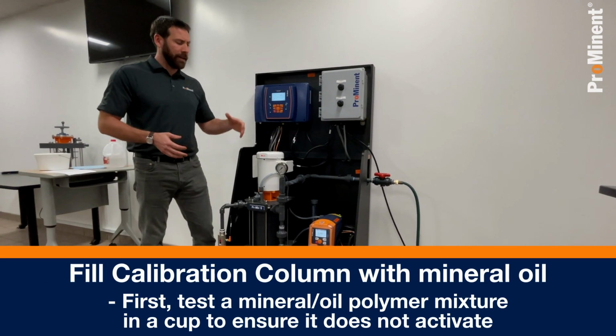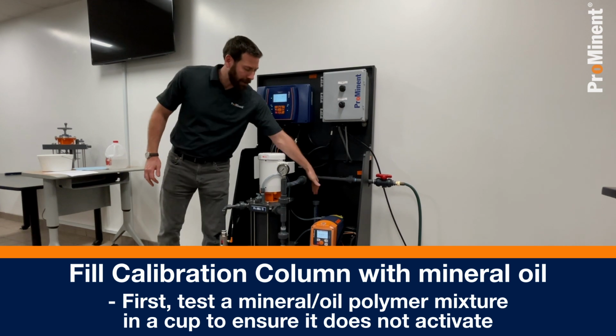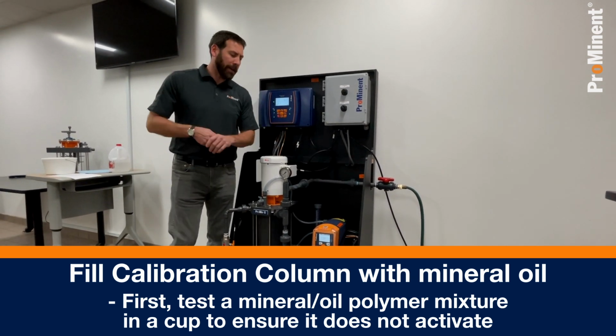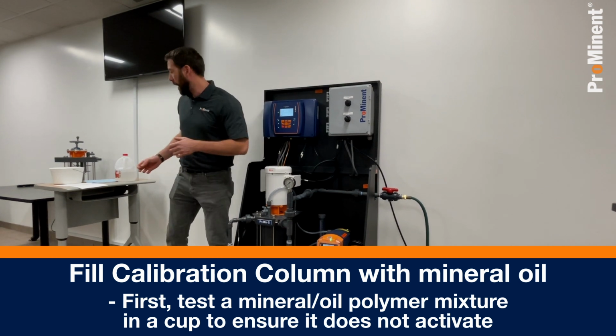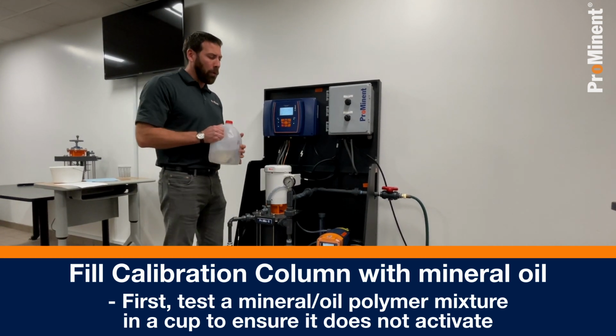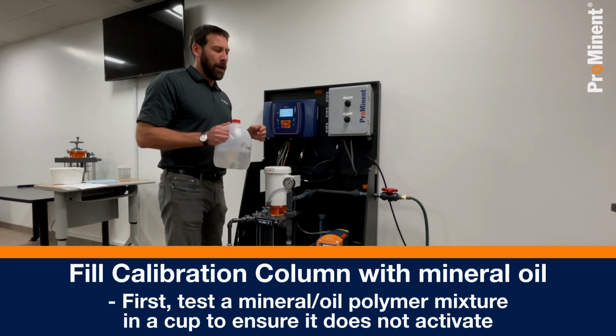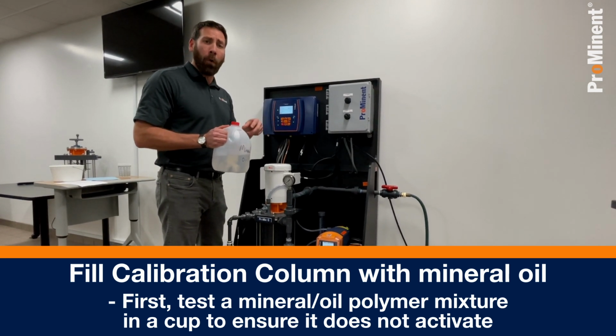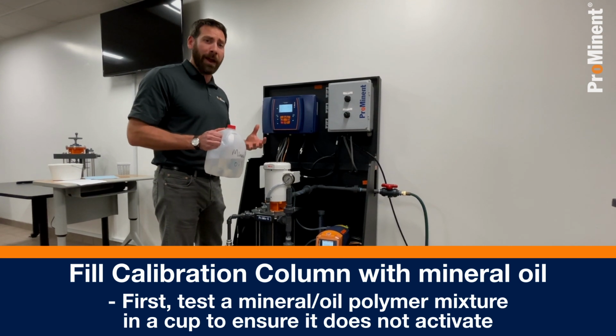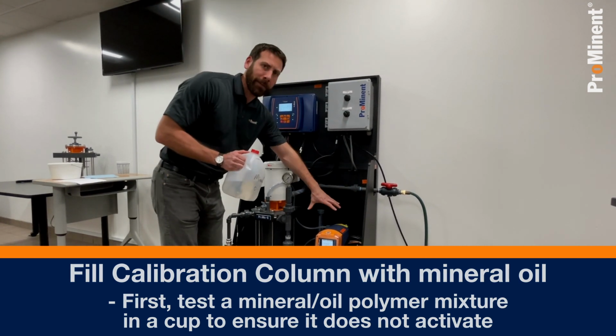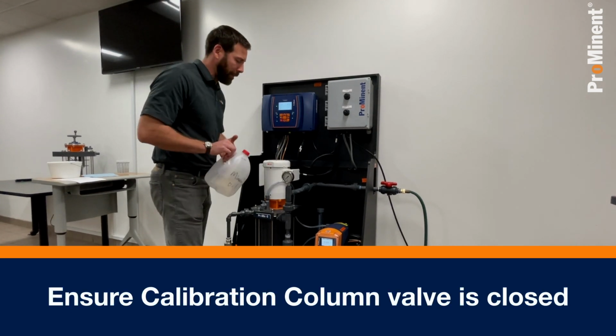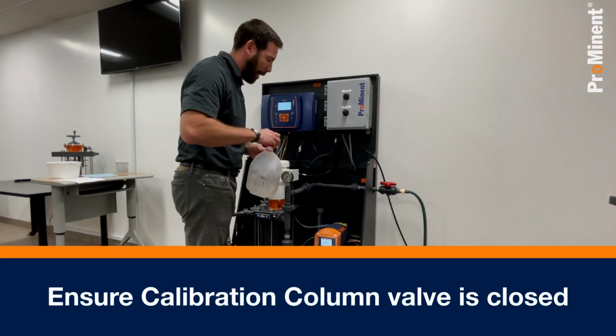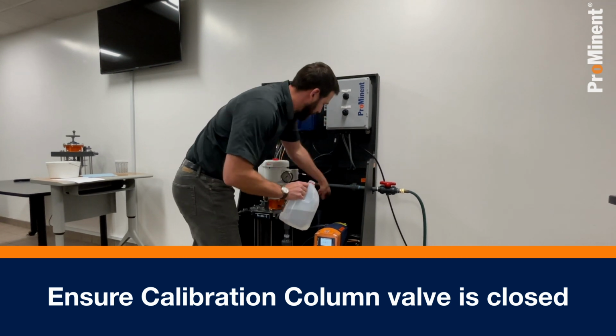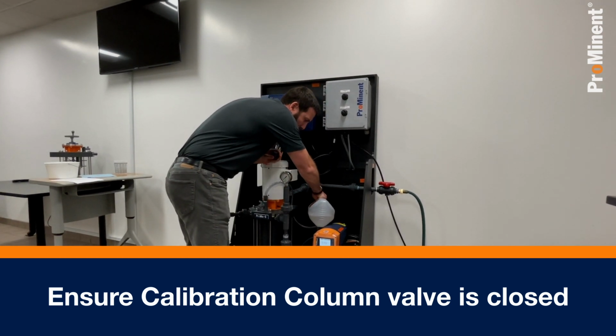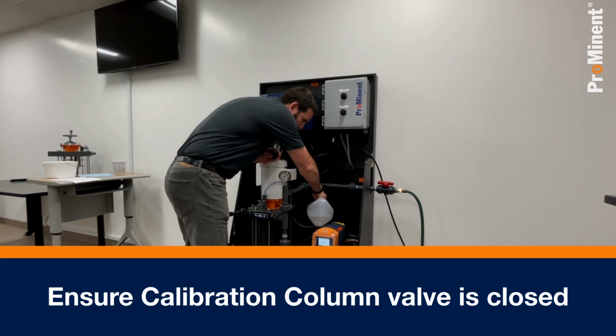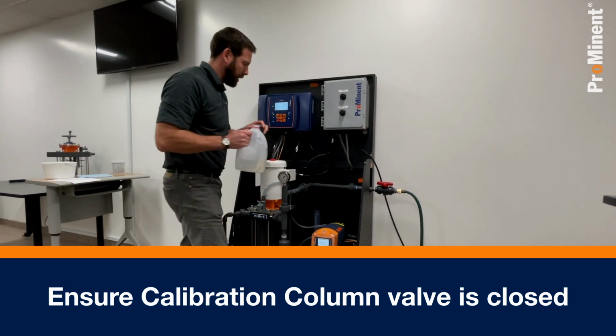Next thing I want to do is fill up my calibration column on my polymer pump with, typically we would recommend using mineral oil. So I have just some mineral oil here. Best practice would be to try a little bit of your mineral oil in some polymer, just in a cup, to make sure it doesn't activate. If it does activate, you don't want that happening inside the pump. So I have my mineral oil, my calibration column is valved out, so it's not being introduced right now. I'm going to take the cap off and then just fill up the calibration column.